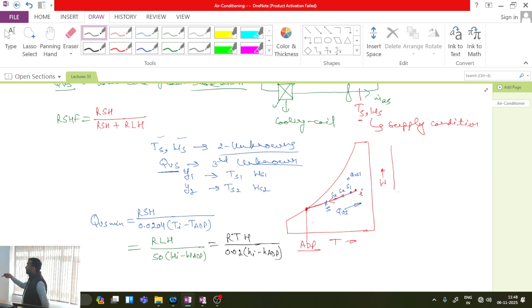Let me assume that QVS is decreased to such an extent that my supply state is converted directly to the apparatus dew point. So QVS minimum will be equal to RSH upon 0.0204 into (Ti minus TADP). That will be the minimum amount of volumetric flow rate which I have to supply. Are all clear with this point or not? In other words, I can also write it in terms of latent heat load, RLH upon 50 into (Wi minus WADP). And it can also be written as RTH upon 0.02 into (Hi minus HADP). So this must be the minimum amount of volumetric flow rate which I must recirculate.